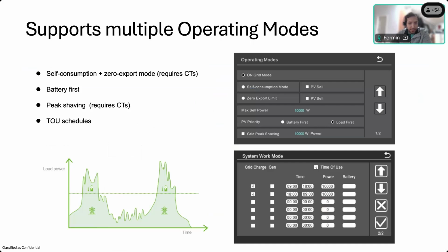You can also set the system to a peak shaving mode. This mode allows you to discharge the battery once the power from your loads exceeds a certain threshold, allowing you to avoid any demand charges from the utility in cases where it's needed. And the system also supports time of use schedules. This allows you to set the system to different schedules according to your energy rates, and be able to discharge the battery at any time.